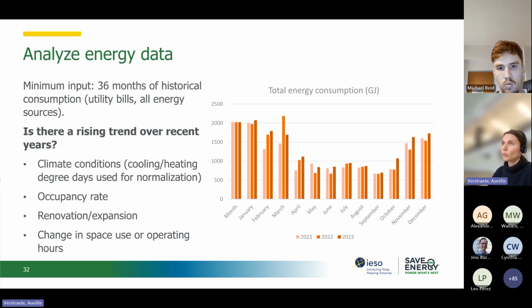So the commissioning provider will see if there are climate condition differences between the years. Maybe ask the owner if the occupancy rates have changed in recent years. For example, if the building was partially empty during year 1, then energy consumption should be lower for that year. Maybe renovation or expansion have occurred. And lastly, maybe there is a change in space use or operating hours that can explain differences.